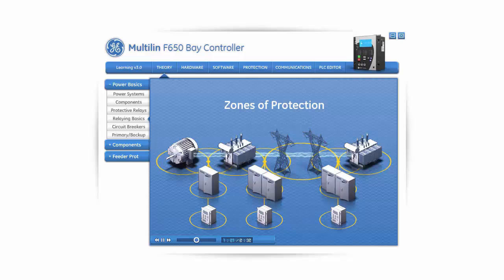For failures within the overlap area, more breakers will be tripped than needed to disconnect the faulty element. However, the overlap areas are relatively small, and the probability of failure in this region is very low. Therefore, the tripping of too many breakers for a fault in the overlap area will be infrequent. The preferred practice is that adjacent protective zones overlap around the circuit breaker, so that for failures anywhere other than in the region of overlap, the minimum number of circuit breakers will be tripped.